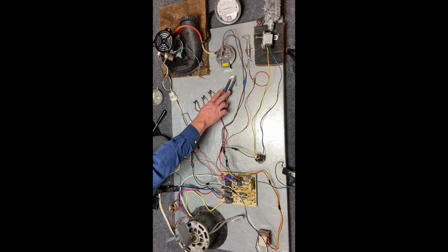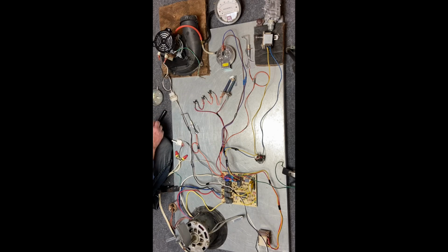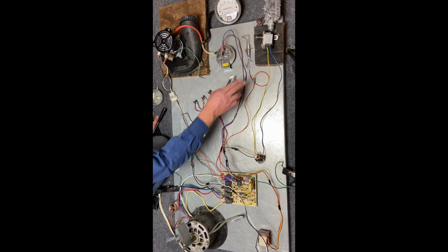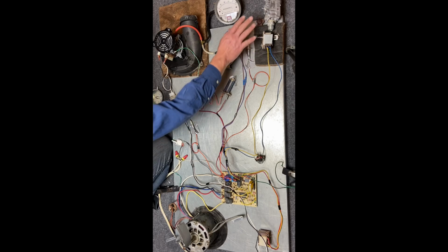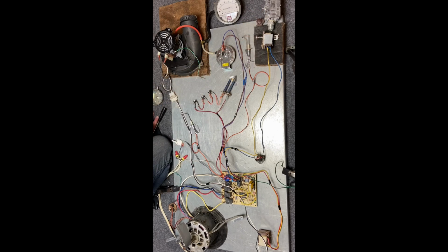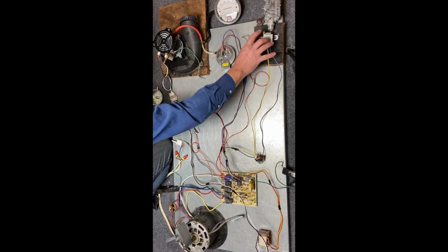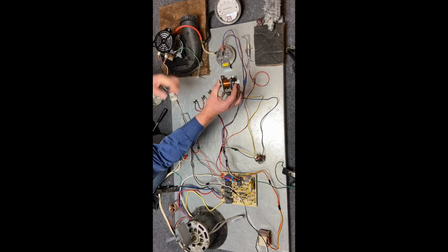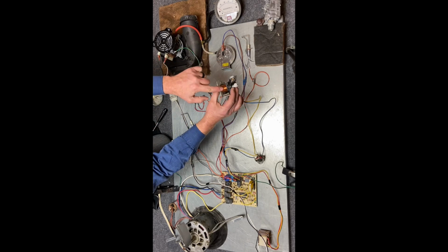This is our primary limit. If this one fails, you need to be thinking airflow, airflow, airflow. Something with the airflow. We're not getting enough airflow. This one automatically resets itself. So again, it's 2 wires, quite simple. Now we're going to look over for our combination gas valve. Now what I've done with the combination gas valve is completely separated it. This is nothing more than a solenoid valve. And if we look here, we can see it's an electromagnet. Even though you're looking at copper wires, each one of these has a coating on it.